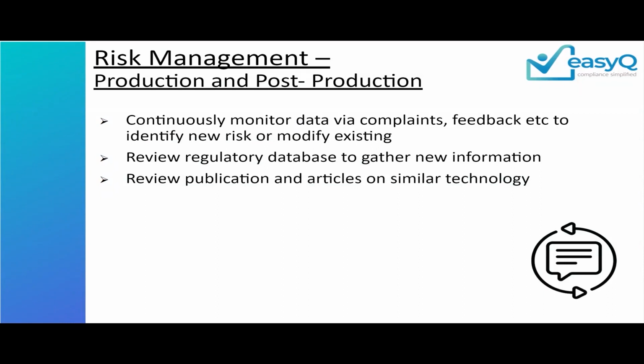So when you keep learning more and more about products, like your product, your technology, or a similar product technology, from where you can adopt certain things, your risk file is but obvious supposed to undergo a lot of adaptation, a lot of changes, right? So from production, post production data, you get that inputs and you ensure that your risk file is always updated, right? This is again one place where people do not do a good job, right? Where they miss out on ensuring that their risk files are maintained properly.